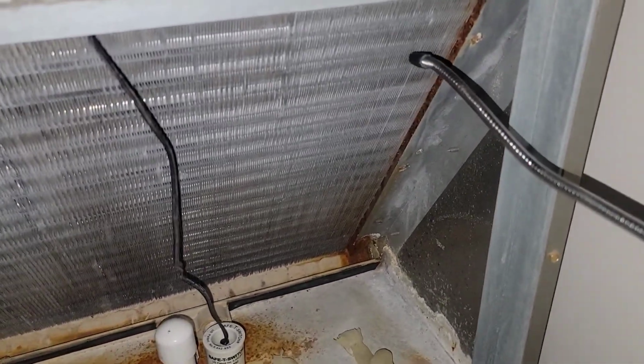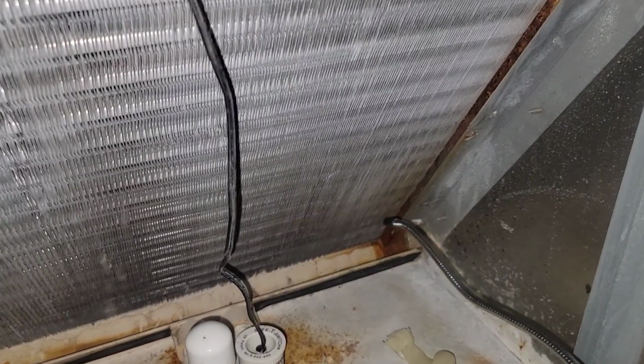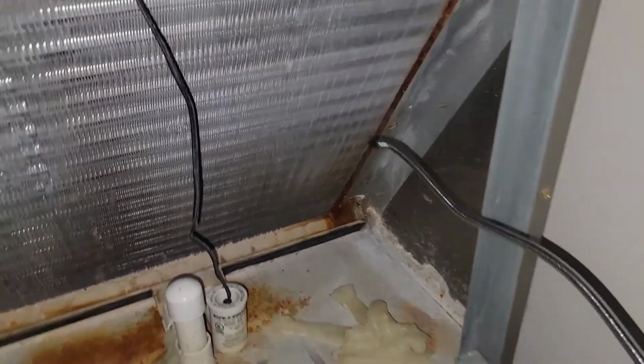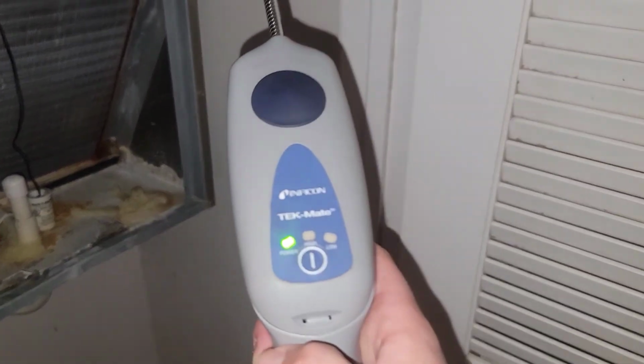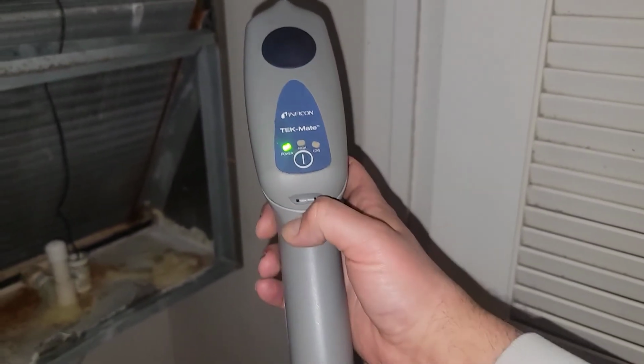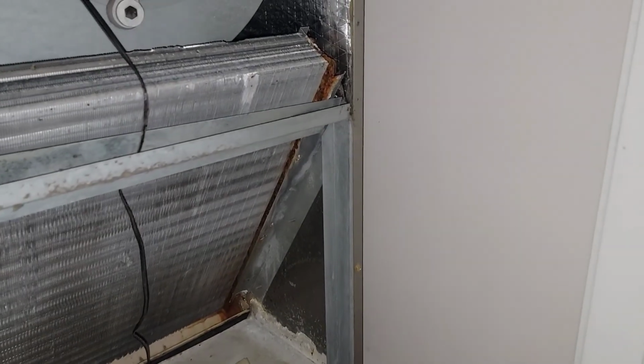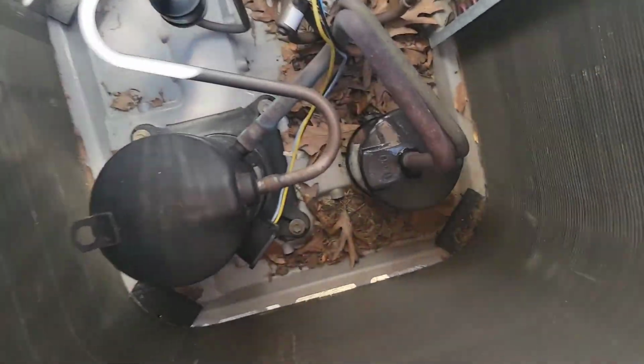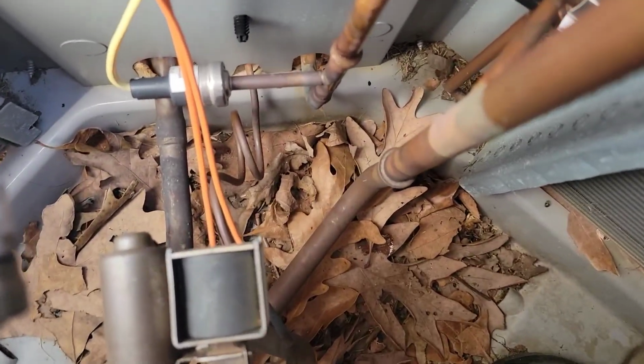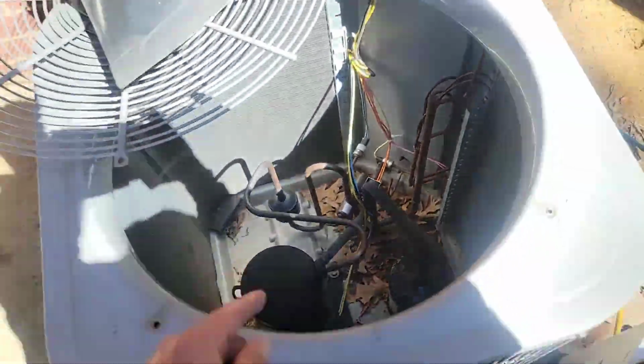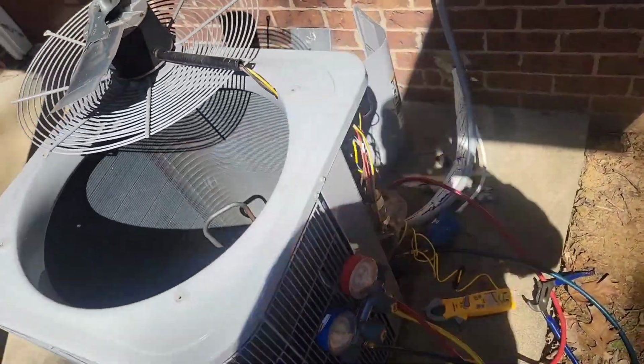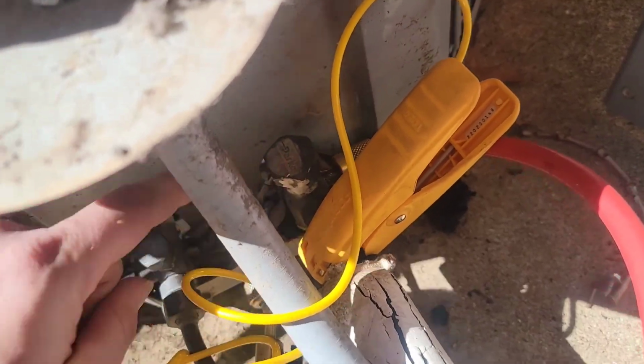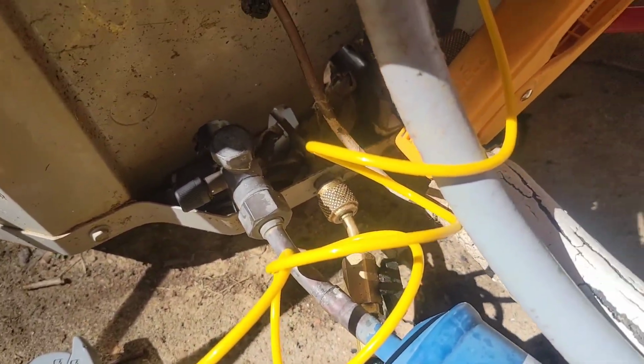The best way is with nitrogen, though. Guaranteed. Nitrogen. But here is the leak detector that I'm using. Let me know what you prefer. Take the top off, look inside, make sure you don't see any oil, any residue, any streaks down the coil. Looks like we don't have any. Make sure there's no wires touching. And also check your service valves, because these can leak as well. So you may have to replace those.